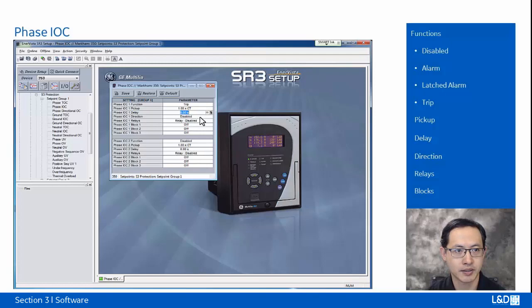to turn on the output relay. The directional setting is used to define the direction of the relay, so this will work with the Phase IOC directional element. We can choose disable, forward, or reverse. And for the auxiliary relays, we can select relay 3, 4, 5, 6. If the trip happens, we can trip the other 4 relays together with trip, or if the function is set to alarm, only the selected relays will operate.